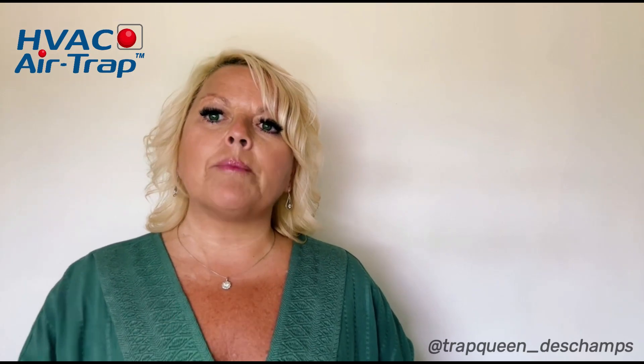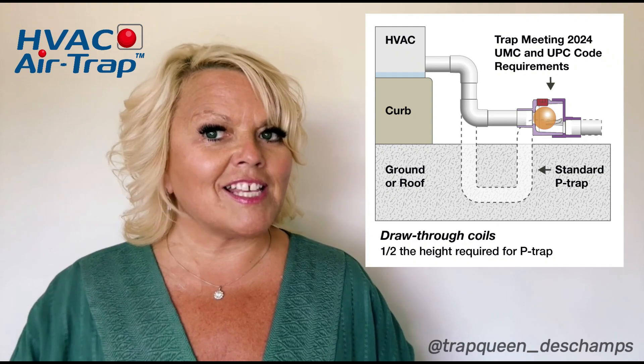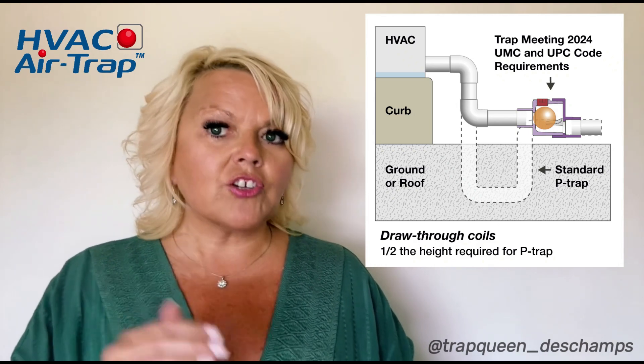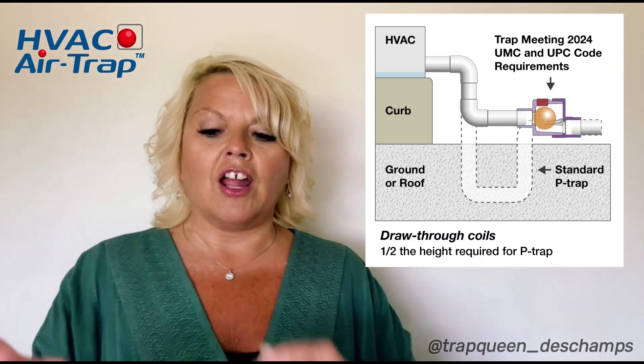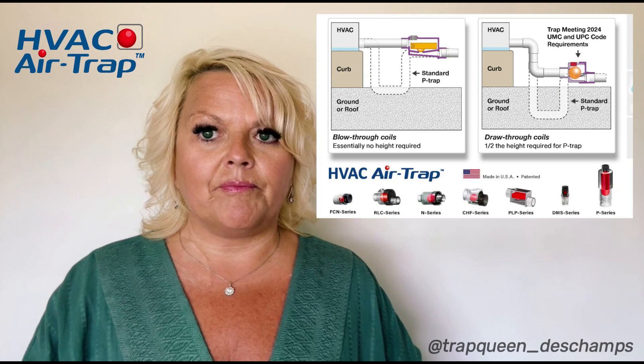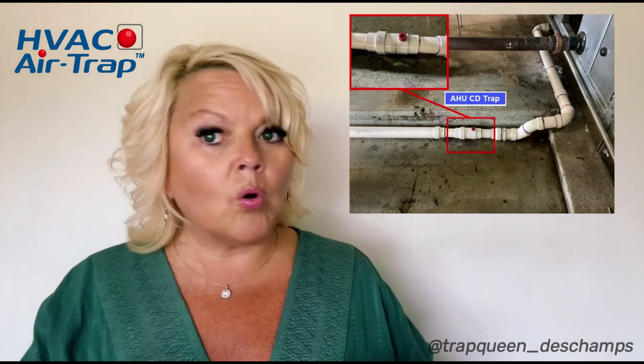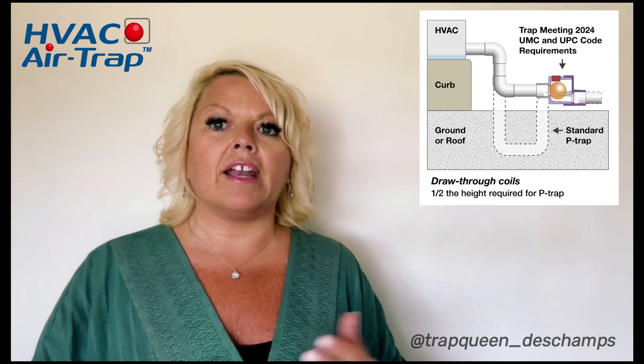Why is it called the air trap? The air trap uses the air pressure of the equipment to maintain the seal. The air trap does not require quite the height that a standard P-trap requires. What the air trap requires is that same static pressure plus one inch for a safety factor — to account for dirty filters, dirty coils, or anything that increases the static pressure. Now you've solved the problem and you don't have to put holes in roofs or jackhammer mechanical rooms to gain enough height. You can see from the image on the screen the difference in space required between a standard P-trap and an HVAC air trap.